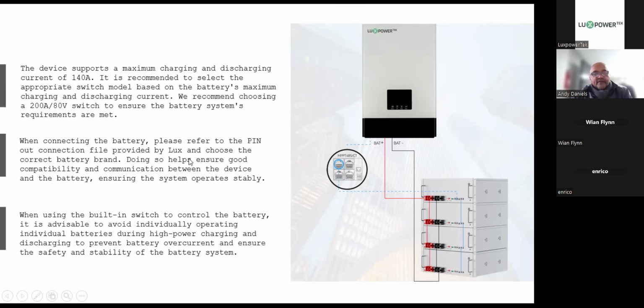When connecting the battery, please refer to the pin layout. Often in our support center, we get requests for what is the pin layout for the various batteries. And also, there are a lot of batteries on the market now that are rebrands or brands that we haven't tested. When you're using a battery like that, remember that the onus is on you, the installer, to make sure that you'll be responsible for the communication if it's not on our list. So for the pin layouts for our inverter, we can do RS485 as well as CAN, and we'll go through the pin layout in a second, okay? But doing the communication helps ensure good compatibility and communication between the device and the battery, and it also ensures the system operates stably.